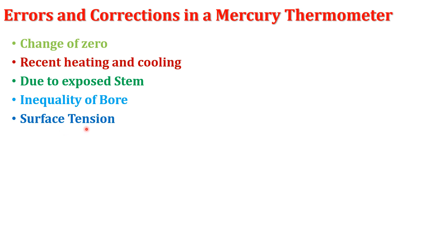The next error is due to surface tension. Since mercury does not wet the wall of the capillary tube, the depression of mercury in the capillary differs at different positions of the stem if the bore is not uniform. To correct this error, thermometer readings should be taken while the mercury column is rising.